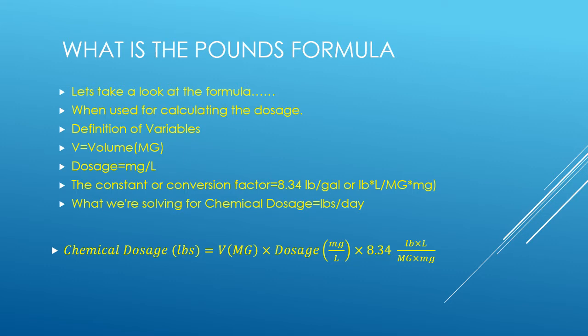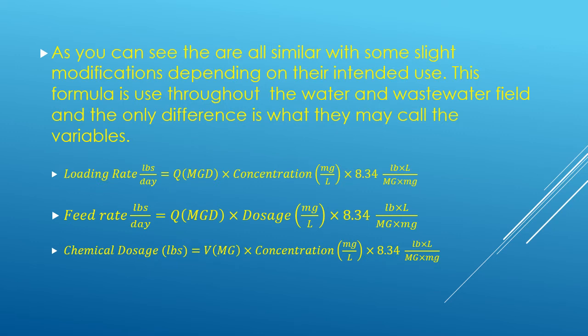Our chemical dosage is a little different but still the same concept. In this one, instead of treating a flow we are treating a volume, and in this case the volume is in million gallons. And of course we still have our same constant, which is 8.34. Again, this is for solving for chemical dosage in pounds per day.